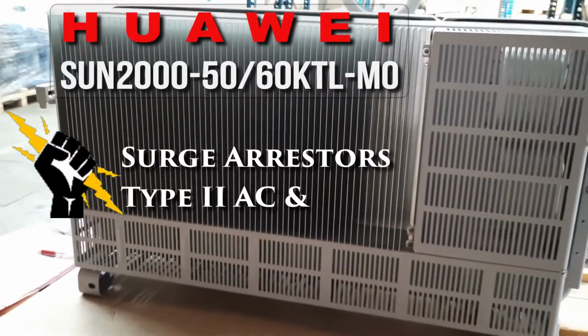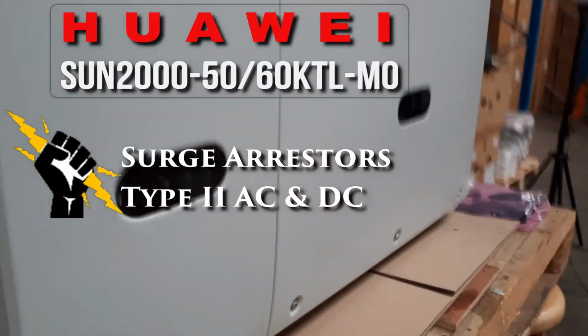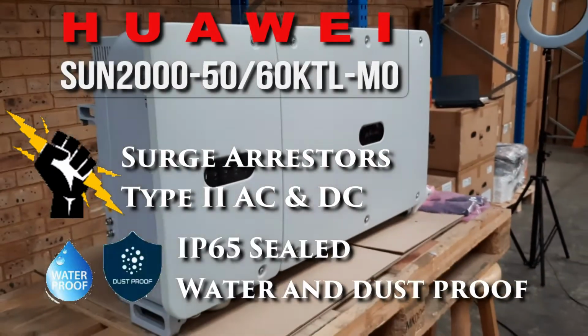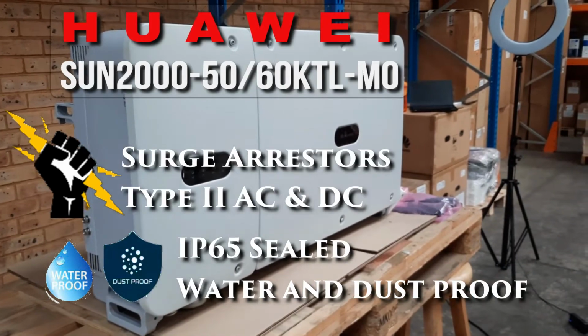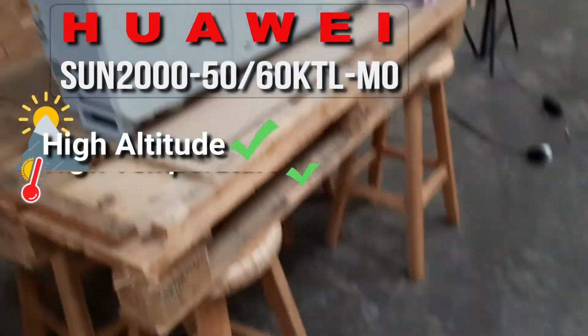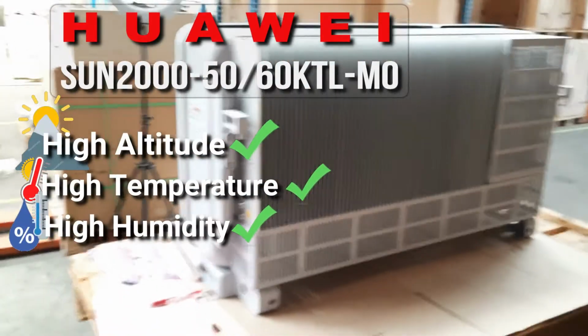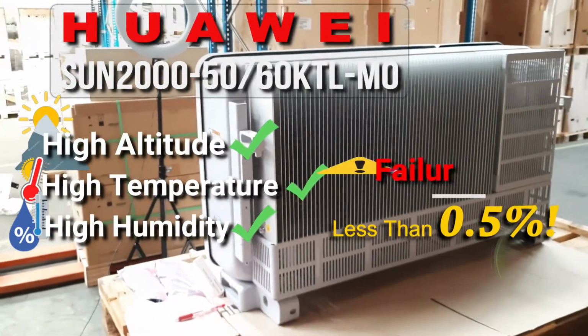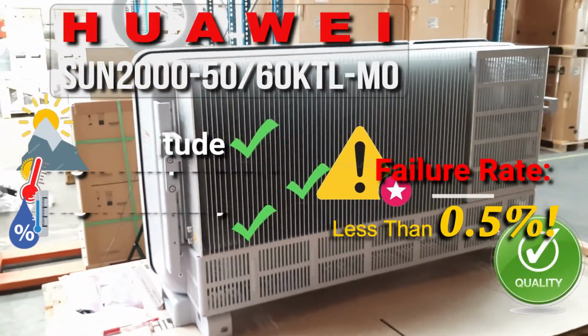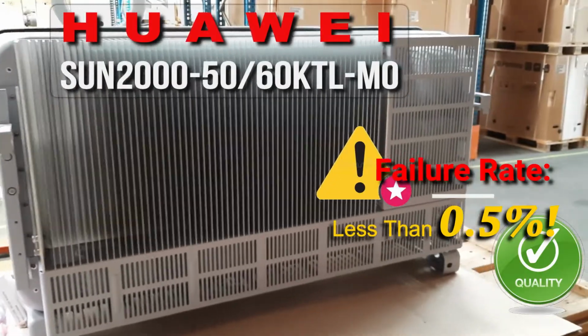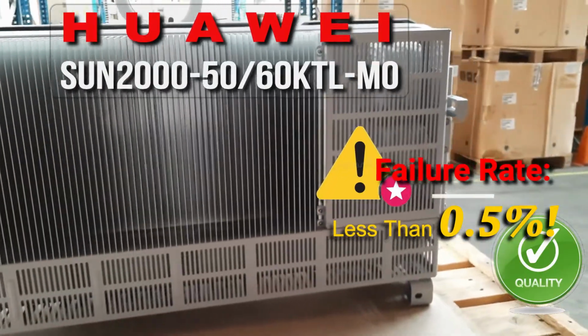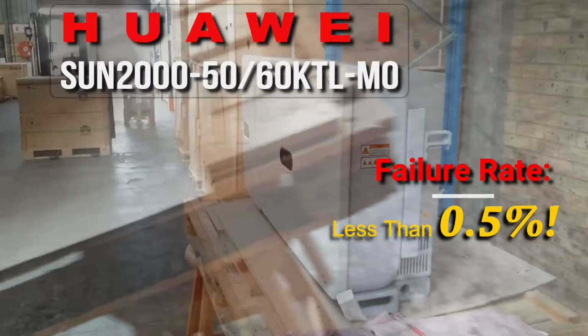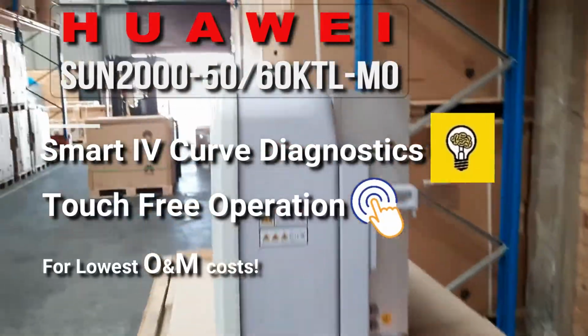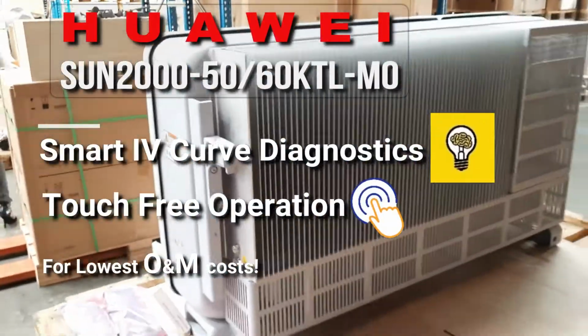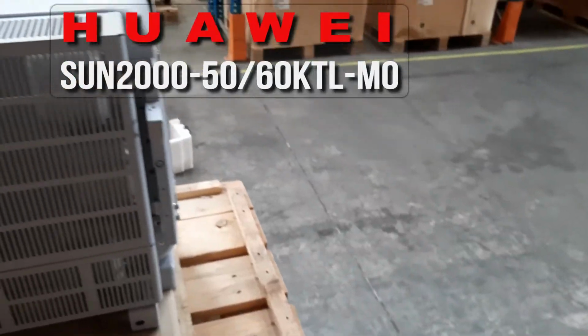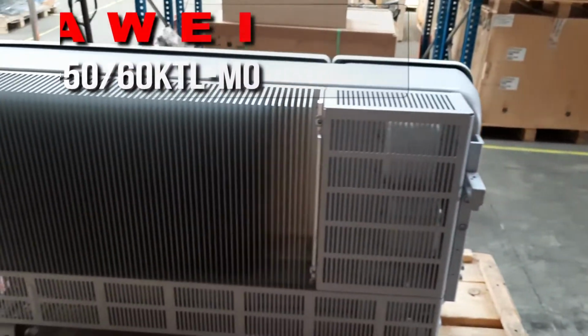It has Type 2 surge arrestors for both AC and DC. The IP65 rating means it's both waterproof and dustproof. This inverter can perform in the harshest conditions. And you get the industry-leading failure rate at less than 0.5%, which means out of 1,000 inverters, less than 5 will have a problem. Now, it also has a built-in IV curve diagnostics and touch-free operation to keep your O&M cost very low. Now let's look at the connections.